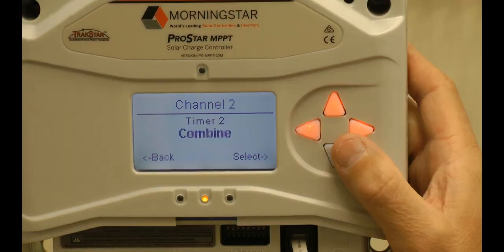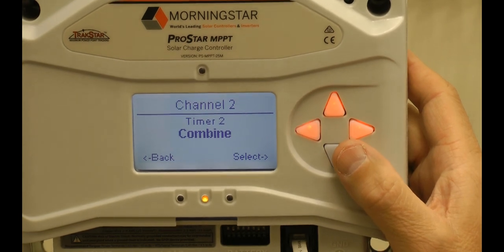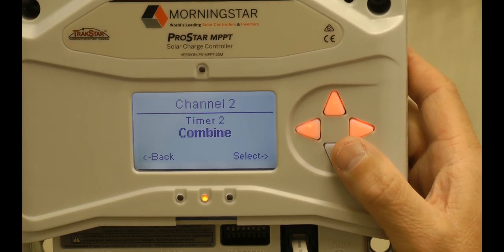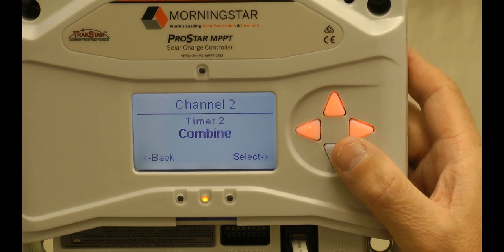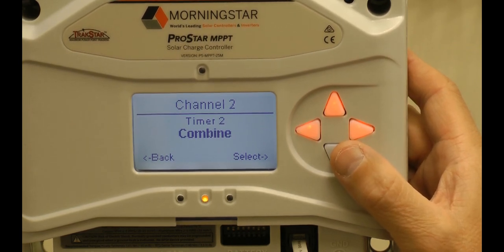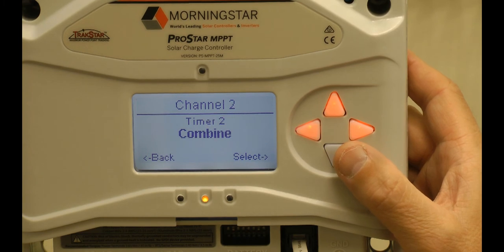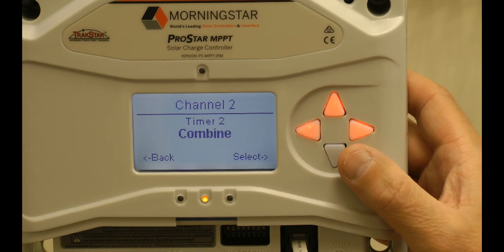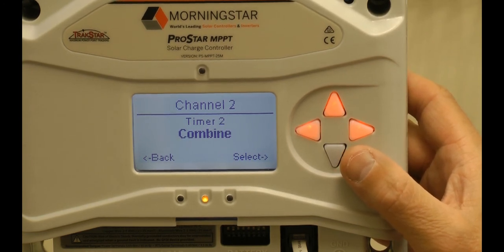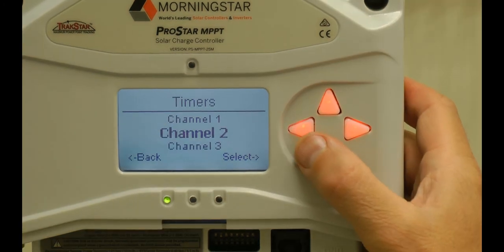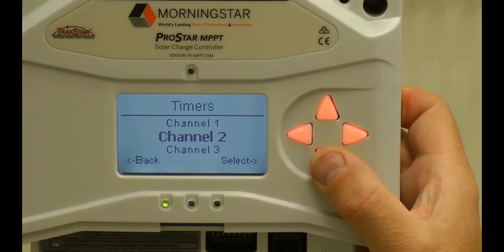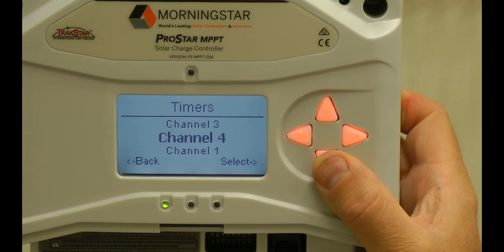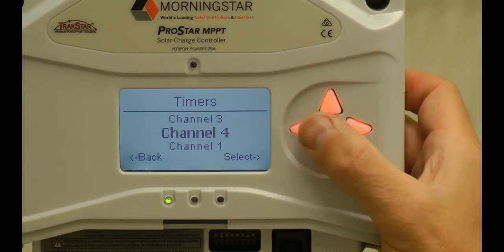I should point out that when you do the combine function, you are combining the channels — combining channel one with channel two in either an OR or AND functionality. It's not that you're combining the timers on a particular channel; the timers on a channel will execute independently. However, the channels have to be told how they're going to combine. We're done programming channels one and two. Channels three and four we're not using, so we don't need to do anything there.